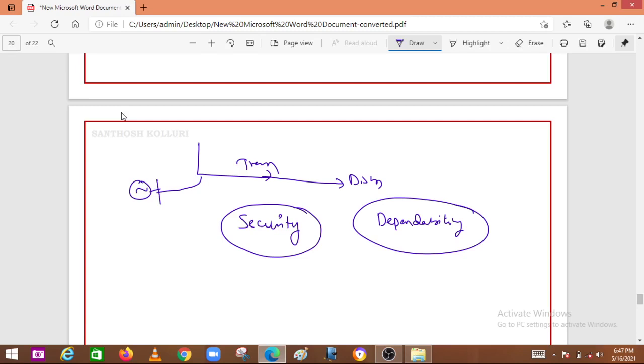Overcurrent relays are not used in transmission system protection, because if you use them there, they face the underreach problem. Because of that reason, overcurrent relays are not generally used in the transmission system. Therefore, overcurrent relays are preferred in the distribution system.